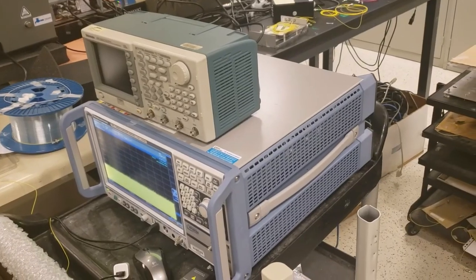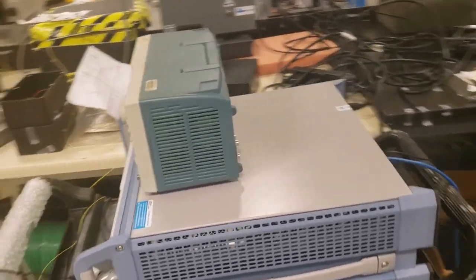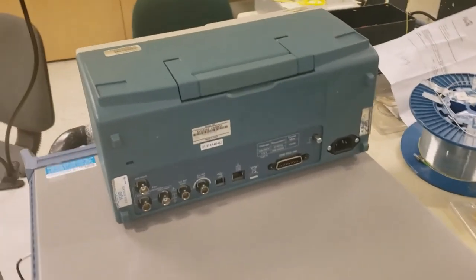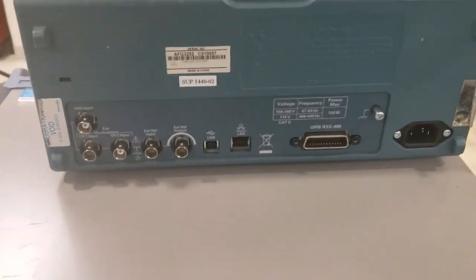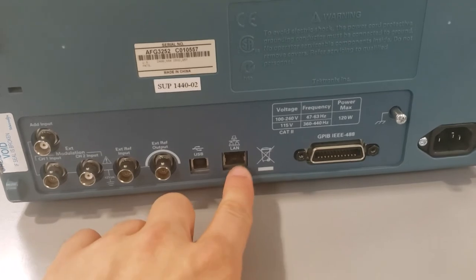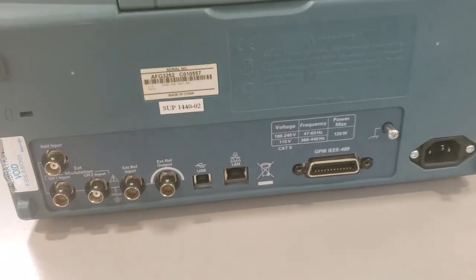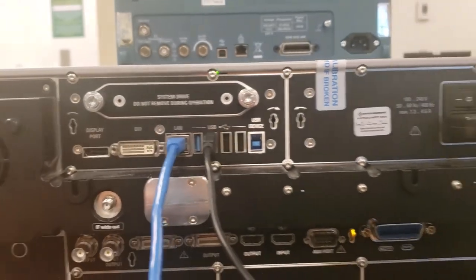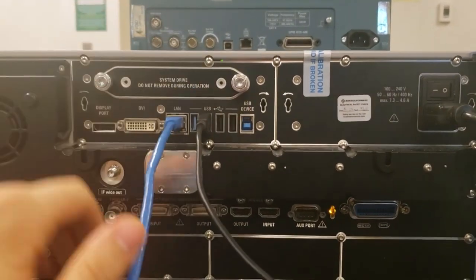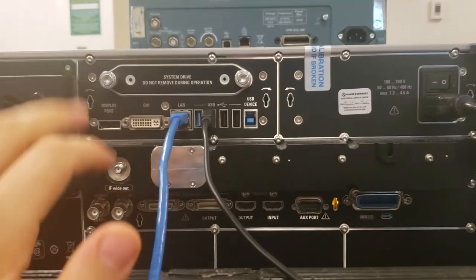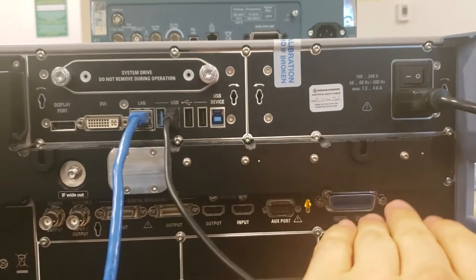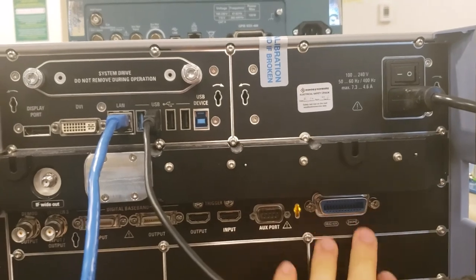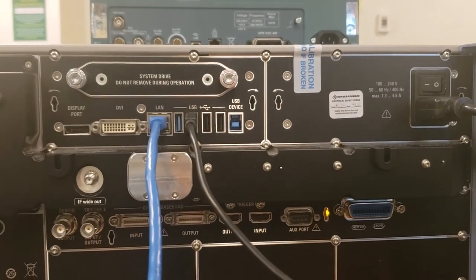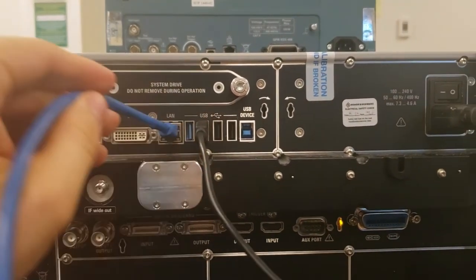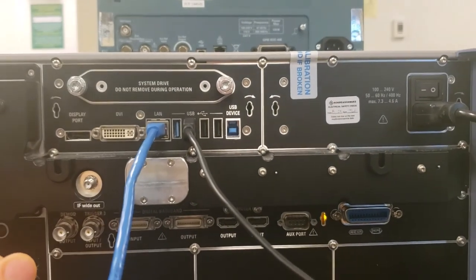Actually, before I go, I should probably clarify that using GPIB isn't the only way you can automate instruments remotely. Most of the modern instruments will probably have a GPIB port, but also an Ethernet port and also a USB port, which can be used to remotely control instruments. And a lot of companies also deliver remote control software with the device, so it depends a bit on the manufacturer. But GPIB ports are a really old standard, also present in a lot of instruments, so I thought that would be the best one to show you guys. But you can experiment with using a LAN cable or USB if you have different devices in your laboratory.